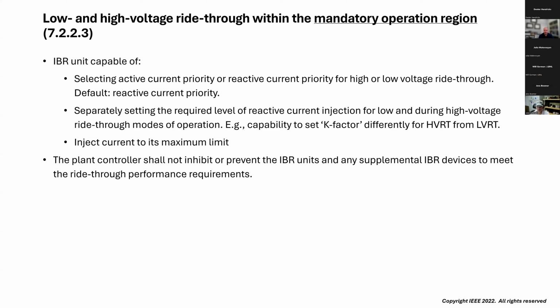Finally, another very important point is the IBR unit needs the capability to inject current to its maximum limit when it's in a mandatory operating region. The example I can think of is you prioritize reactive current. You meet the control objective for reactive current, but you drop your active current to 0. That's not what is required, and it's explicitly stated later in the standard. You want to be able to use the remaining current carrying capability up to the maximum limit.